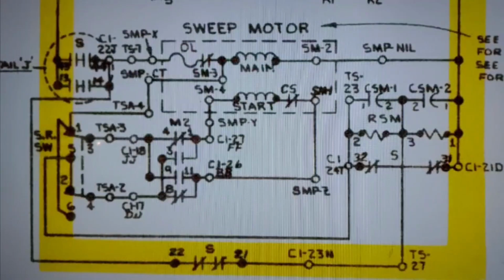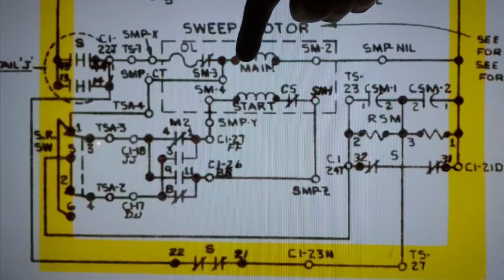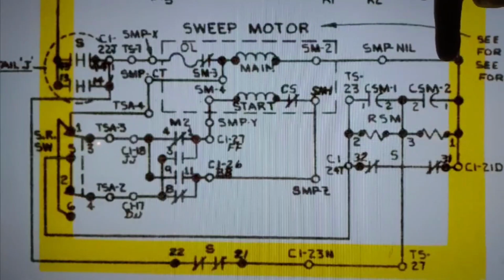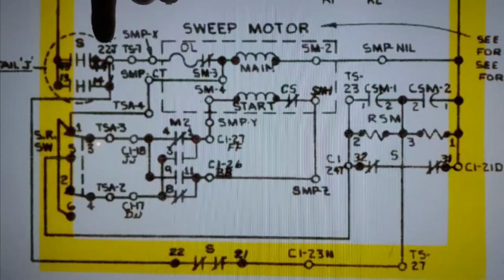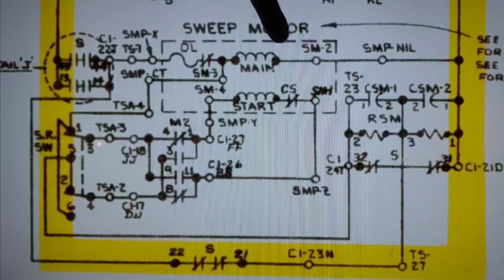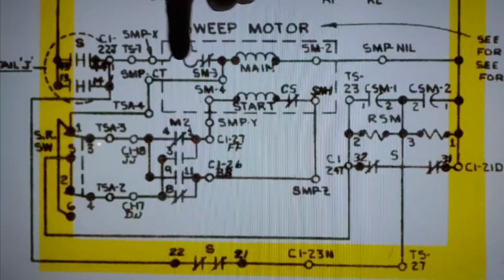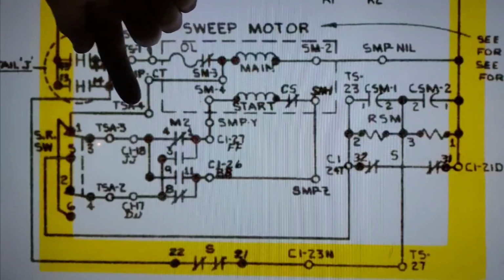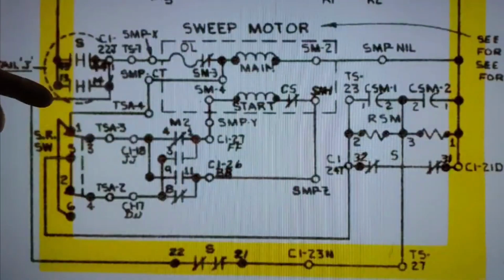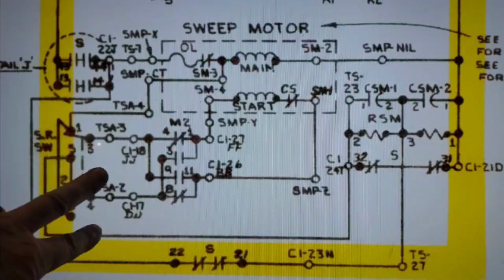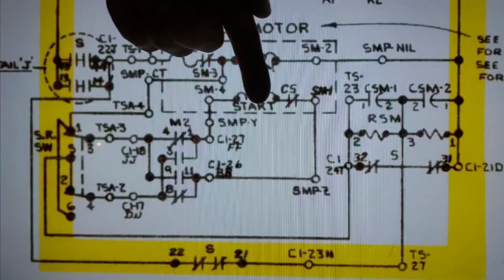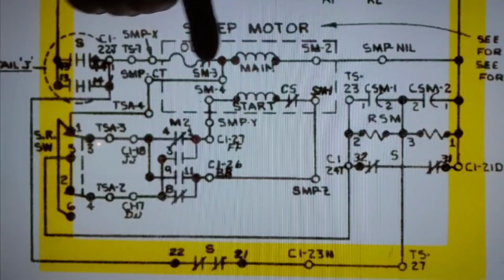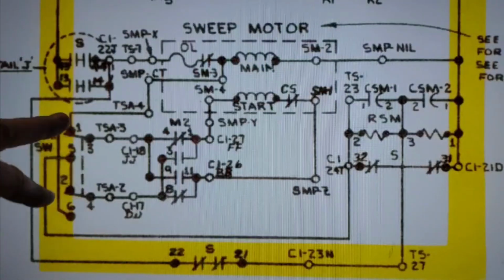Again, now because ours is going to be fancy with little cams and actual motors, the main is going to be our synchronous motor. So one goes straight to neutral, the other one is going to come out as 22J. That's what's going to power our little motor. So we're going to steal off of 22J, as you see here, after the overload. It goes out center terminal, down to the terminal strip, over to the mechanics terminal strip to the mechanics, and all that does is flip the polarity of the start winding, so we can spin the motor in reverse. That's all you're doing with your switch, is flipping the winding.